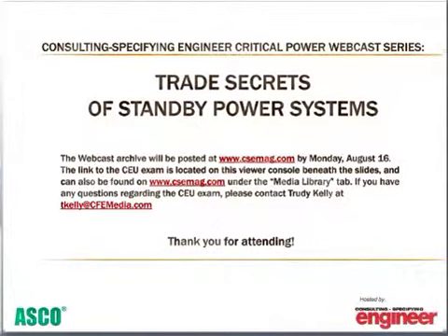Breakers are going to be 3-pole. So we see a lot of clients using 3-pole ATSs in large mission-critical facilities, and that is certainly okay. You just have to be aware that you will not call your generator a separately derived system, and you have to be aware of some of the potential consequences of doing that. But the superior method is to provide a 4-pole transfer.